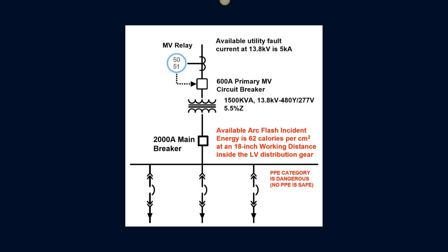So this shows a typical physical main configuration. And I want to point out that the National Electric Code makes absolutely no distinction between a physical secondary main and a secondary virtual main. Both are allowed, both have the exact same functionality and efficacy in terms of overcurrent protection. So in this case, with a Y secondary, we have to provide overcurrent protection within 10 feet of the transformer, and that's done, as you can see in this example, with a 2,000 amp main breaker.